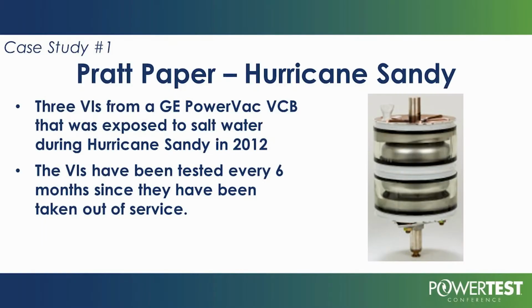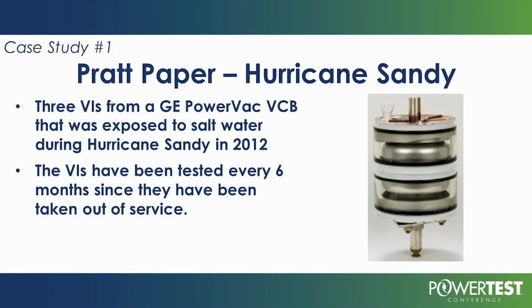The particular interrupters that came out of Hurricane Sandy came out of a paper plant in the New Jersey area. These interrupters were submerged in water for a short period of time, so we've done everything we could to a couple of them to slow that degradation by using processes and materials to slow that corrosion. Then a few of them we've let them just corrode to see what the delta is between ones that we treat with a particular substance that we think is going to preserve the stainless steel and the brazing filler materials and cause them not to fail. So we've seen pressures differ between the ones that we've actually processed with a chemical that we'll be talking about in a future paper. These interrupters have been tested every 6 months, so we have some particular data that's over 9 years old on them.